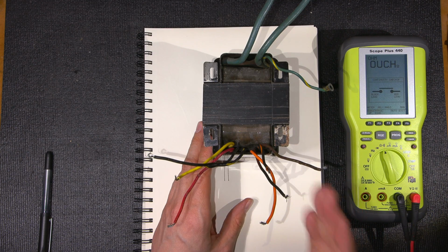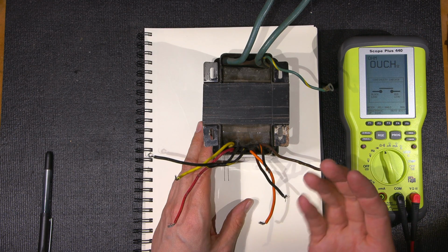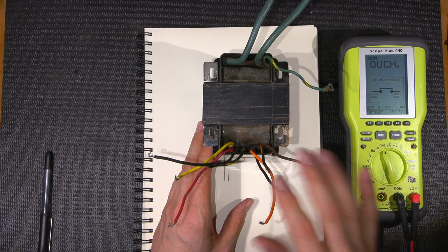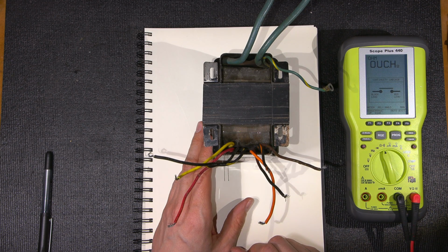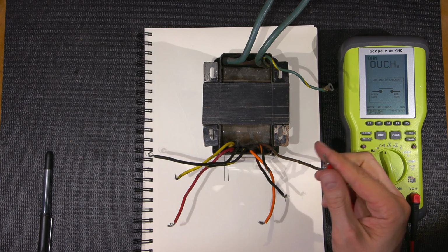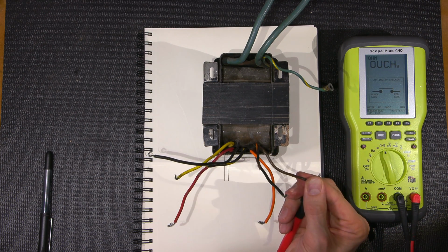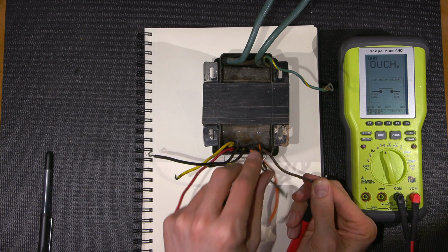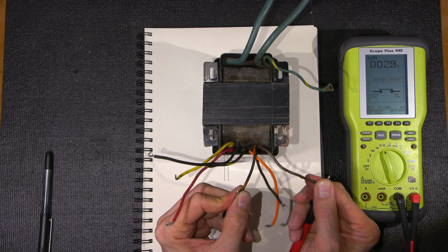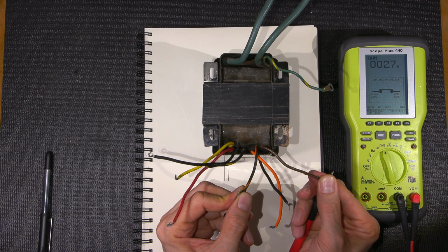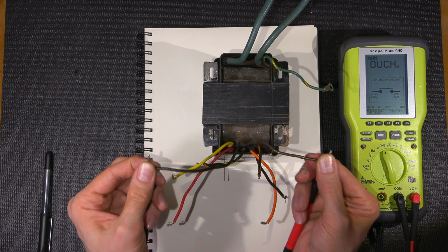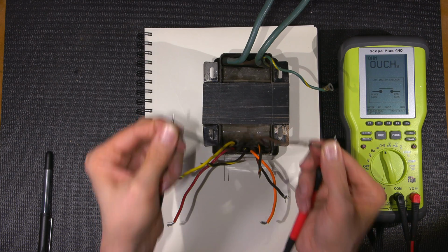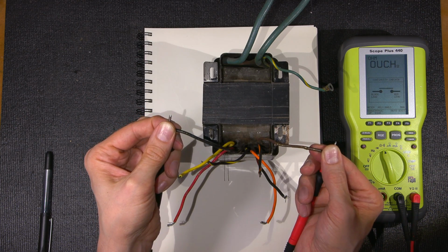So how we're going to locate this right now is we're going to see if we can find an open connection between at least 2 of these wires. If there is, then we know we have 2 separate windings, and then we can split the windings up. So let's find out. I'll attach my lead to brown, and let's just try this one here. Oh, there's a connection there. So let's go between brown and black. Aha, no connection. So we have 2 separate windings here.